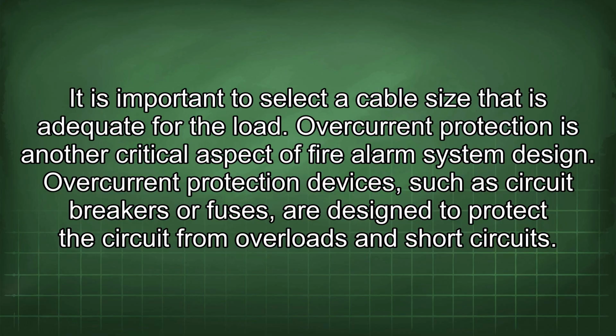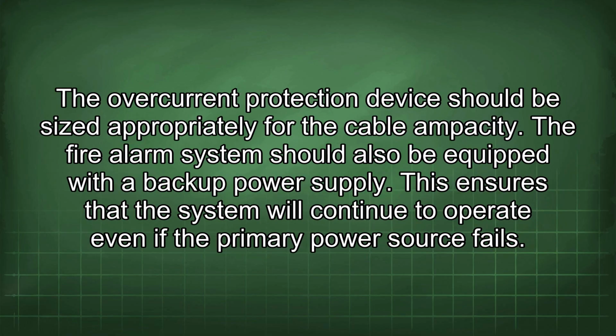Overcurrent protection is another critical aspect of fire alarm system design. Overcurrent protection devices, such as circuit breakers or fuses, are designed to protect the circuit from overloads and short circuits. The overcurrent protection device should be sized appropriately for the cable ampacity.